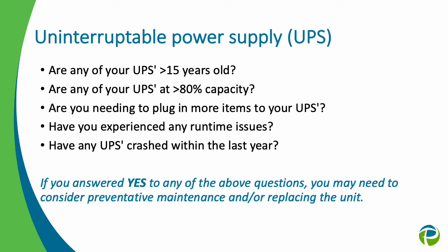Are any of your UPSs at greater than 80% capacity? It is never recommended to load your UPS more than 80%—that is definitely the maximum. So we'll want to look, is that happening? And if it is, we will definitely recommend you either need a new UPS, or maybe we need to add a dual redundant system, so you have two UPSs splitting that load.